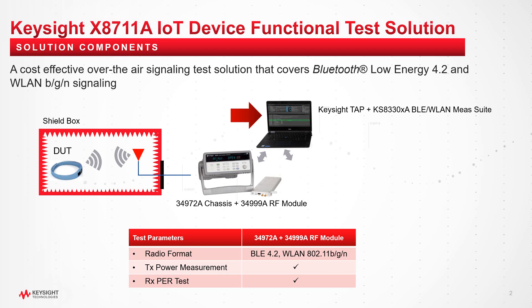The 34999A RF module is connected to a PC for automation tests using the ready test program that is built based on the Keysight TAP platform and measurement suites. Or you could develop your own test program to automate the testing using the 34999A driver. It is a .NET DLL programming interface and can be installed through the X8711A install wizard.